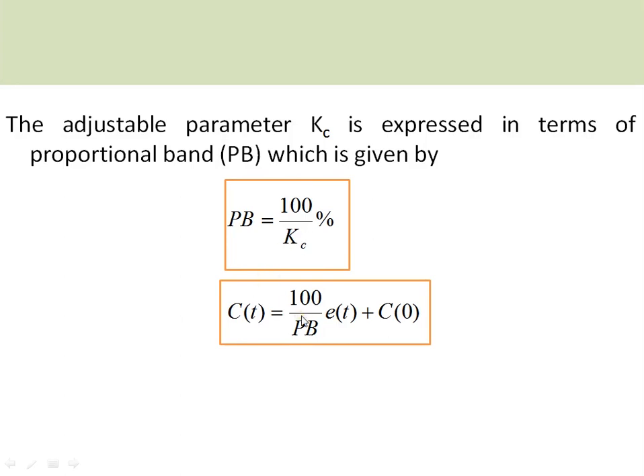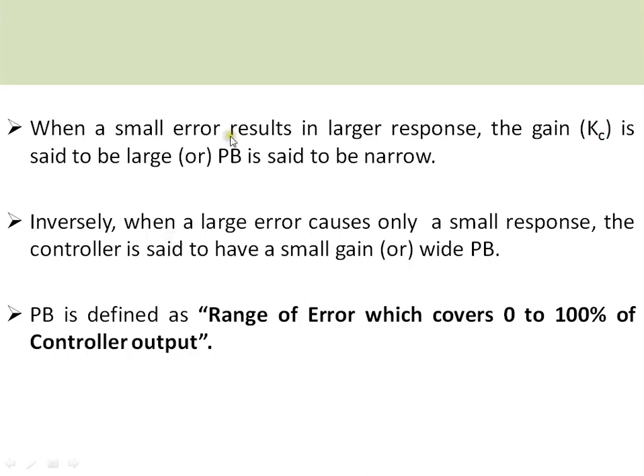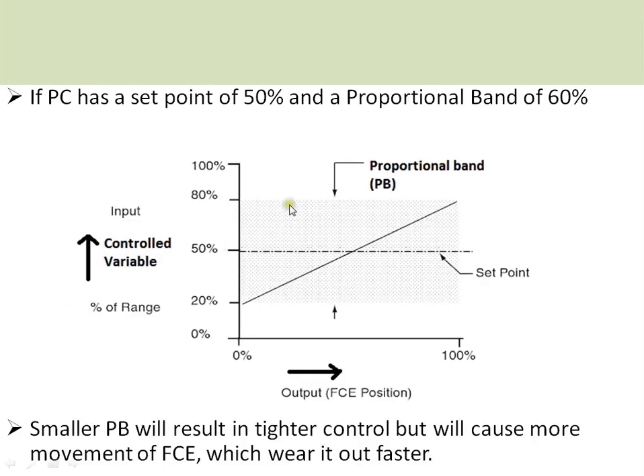The proportional band can be set based on the required response. When the gain is large, a smaller error results in a larger response — this is a narrow proportional band. When the gain is small, a larger error causes only a small response — this is a wide proportional band. The proportional band is defined as the range of error that covers 0 to 100 percent of the controller output.